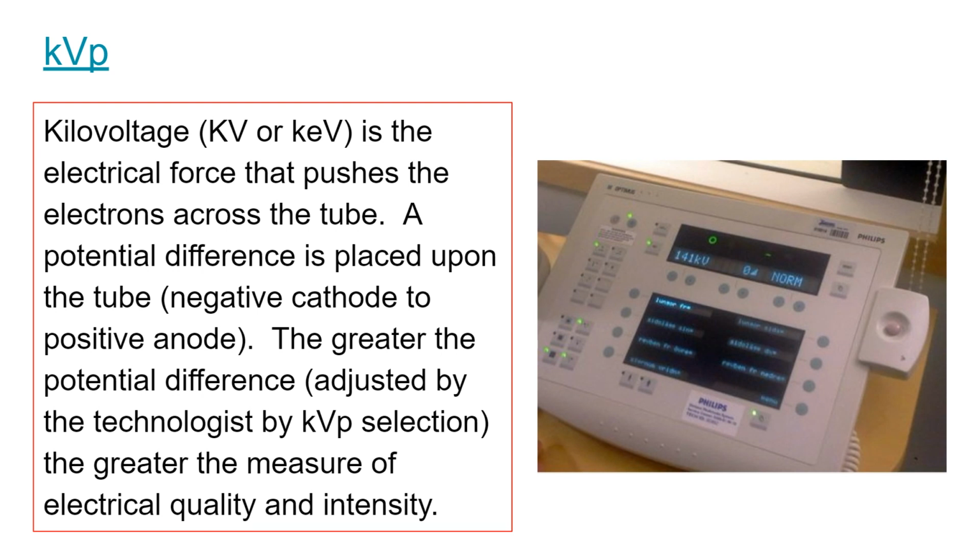It's that push. Actually, in the lab, someone asked me a good question. When the MA and time are set, the time governs essentially how long the MA continues to be applied, like how long the filament continues to stay on. But it also means the KV stays on, because the question was, what happens with the KV? The KV also stays on for the duration of the exposure. Because what good would it be if you continued to create electrons thermionically, but they just sat there and weren't pushed over because the KV stopped kicking in?